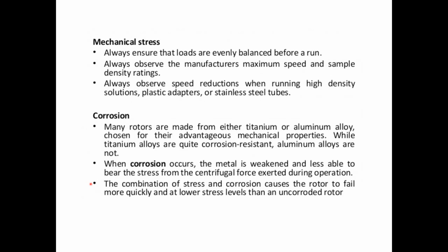What you have to avoid is mechanical stress, and that means that the loads have to be evenly balanced before a run. And that usually you do with a balance and not by eye. And don't forget, when you load gradients, the balance tube on the other side of the rotor that you need to counterbalance your weight cannot just be filled with water. It has to be filled with an entire gradient, with the identical gradient.